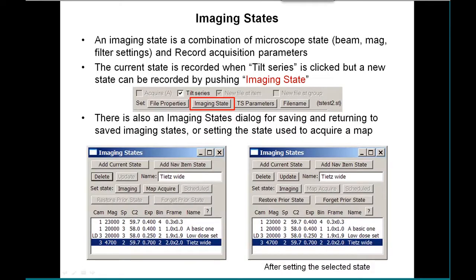The button I didn't mention was the imaging state button. Imaging state refers to a combination of the microscope state — the beam, magnification, any filter settings — and the record acquisition parameters. It's the whole set of information needed to reacquire a picture under known conditions. When we go to realign to a map, it goes and sets the imaging state of that map. When you check tilt series for one of these locations, it automatically records the current microscope state as the imaging state. If that isn't right, you can readjust the microscope and press the imaging state button for that item.